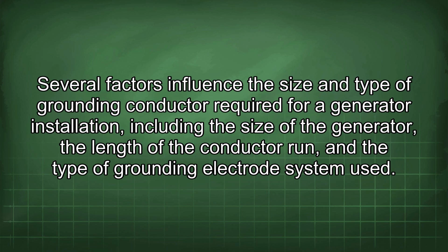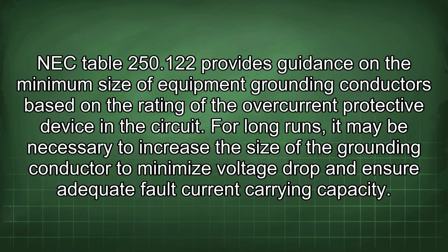Several factors influence the size and type of grounding conductor required for a generator installation, including the size of the generator, the length of the conductor run, and the type of grounding electrode system used. NEC Table 250.122 provides guidance on the minimum size of equipment grounding conductors based on the rating of the overcurrent protective device in the circuit. For long runs, it may be necessary to increase the size of the grounding conductor to minimize voltage drop and ensure adequate fault current carrying capacity.